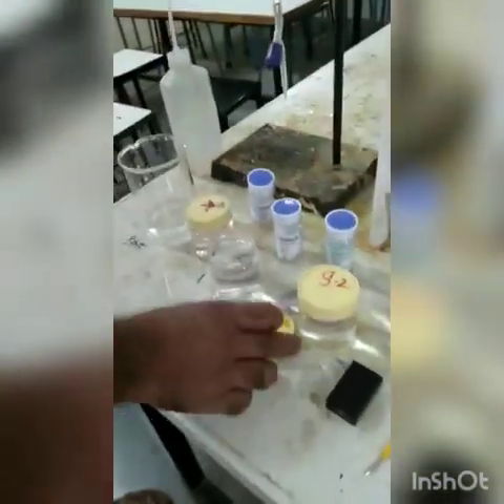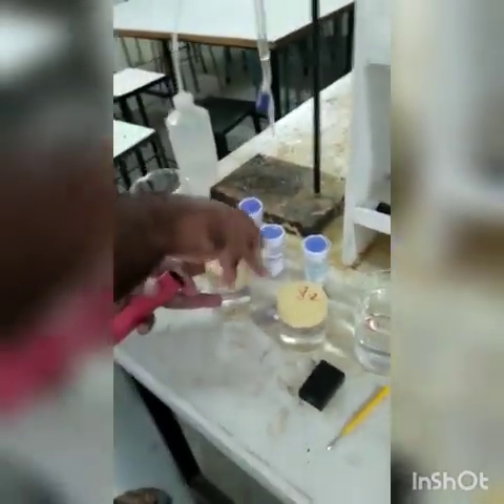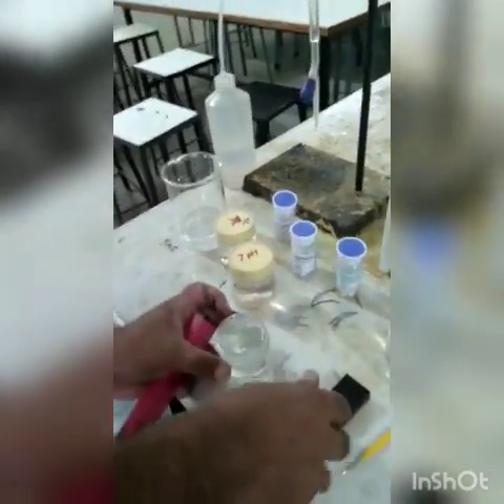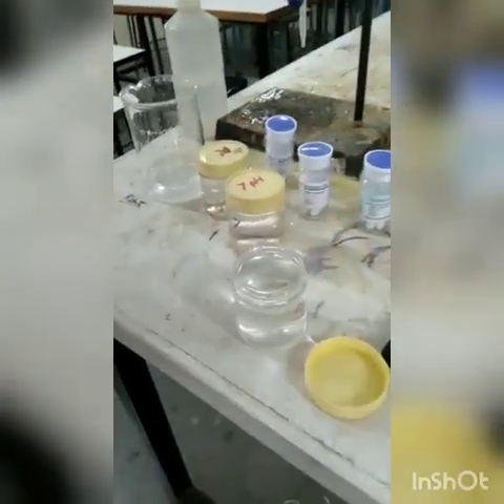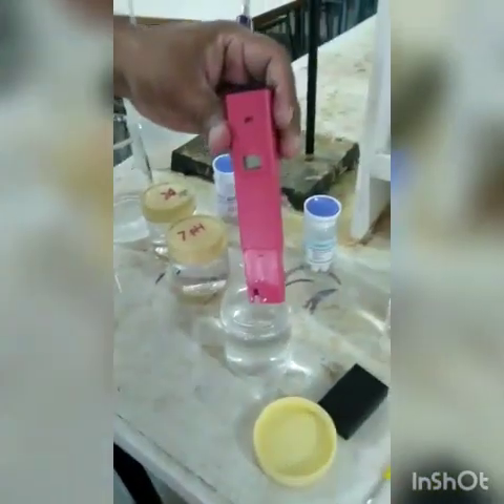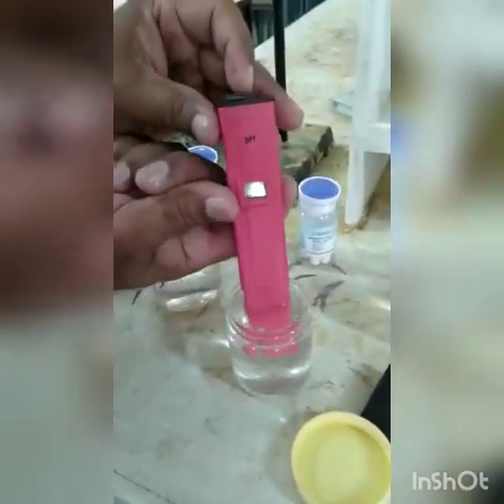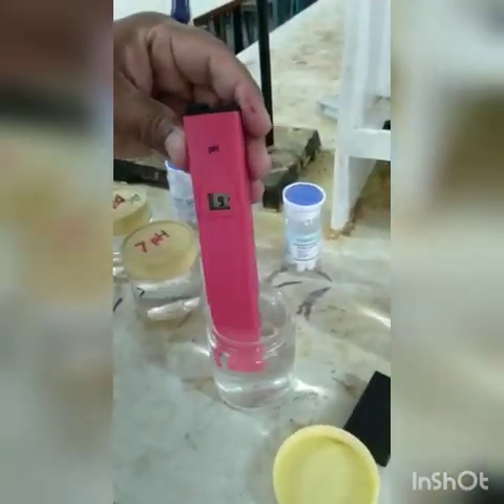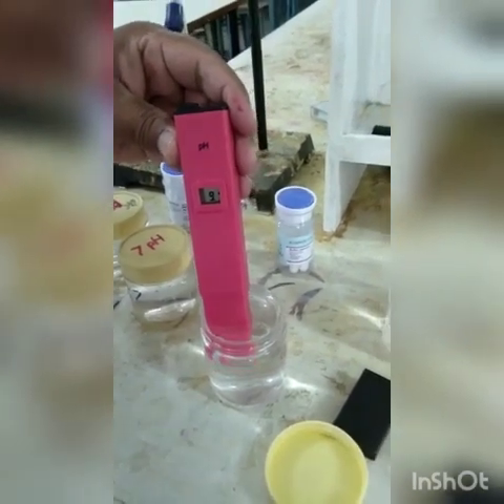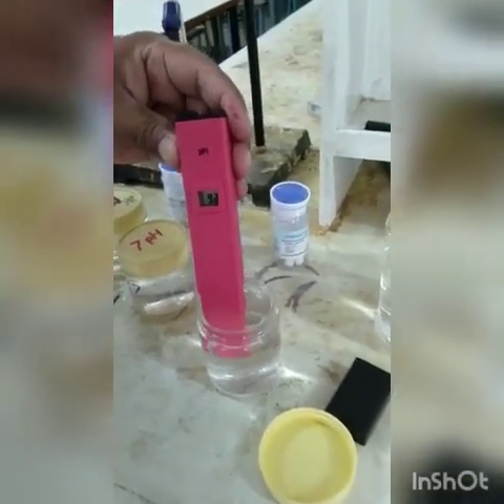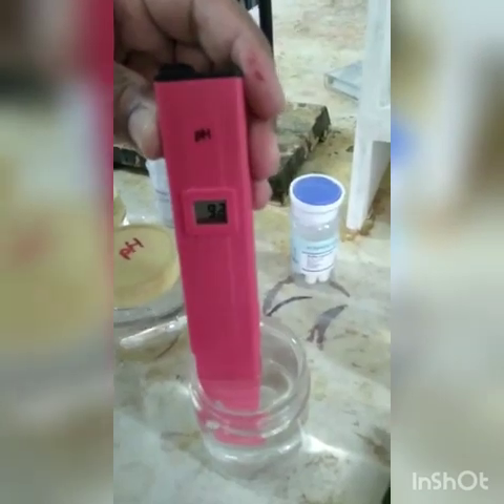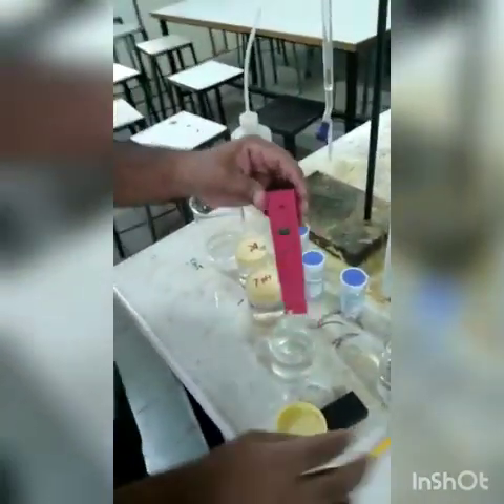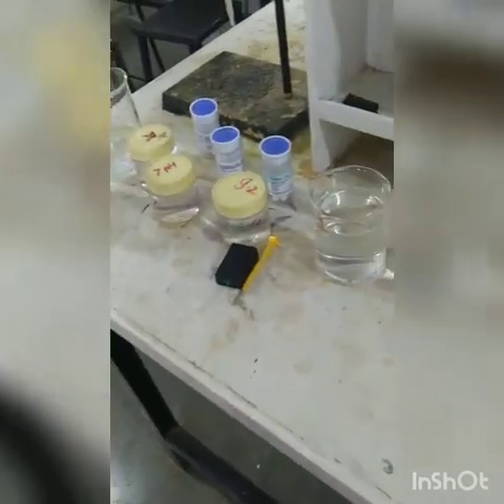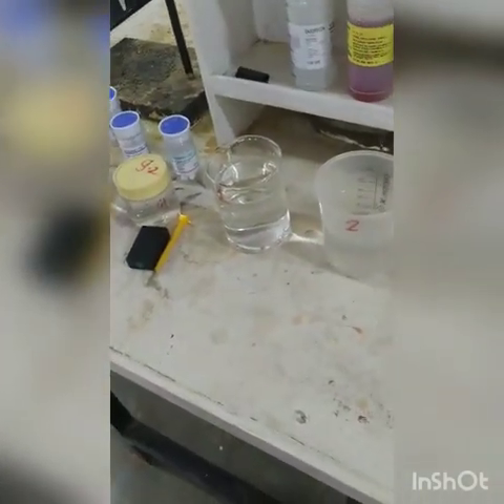And now use it for calibrating with the pH value of 9.2. So again the probe will be dipped. Again a micro adjustment will be done with a screwdriver. Yeah, it is already showing 9.2. So our instrument is calibrated now. So now we are ready with the measurement of actual samples.